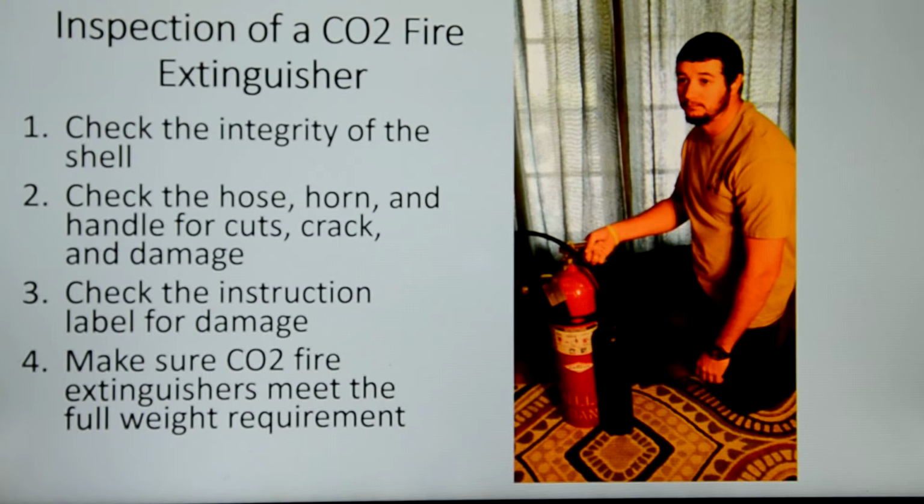And make sure the CO2 fire extinguisher meets the full weight requirements. Also check your tag, make sure it's inspected this month, and your safety seal. Here's another short video of how to inspect it.